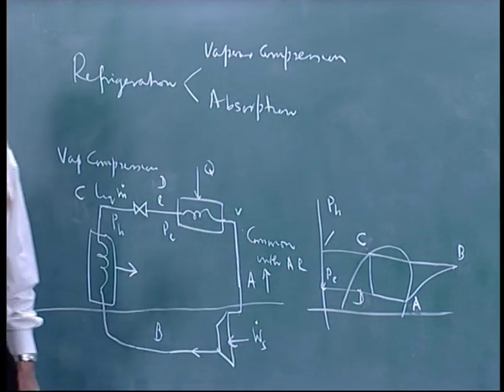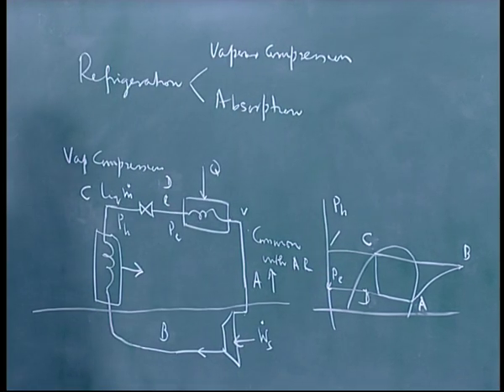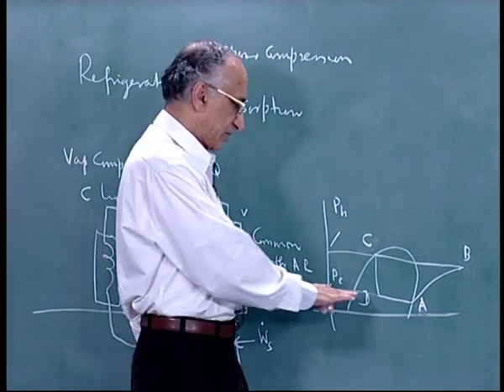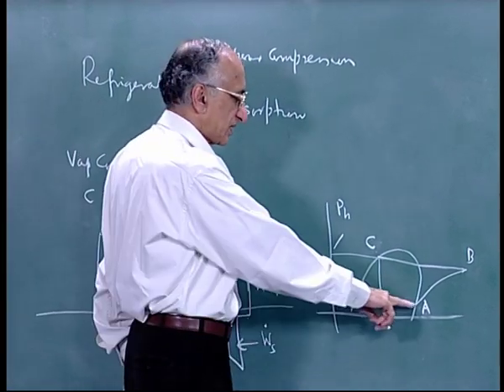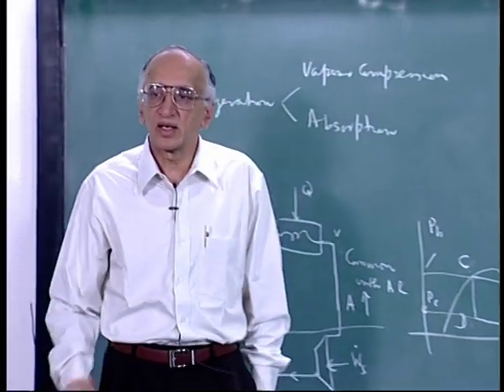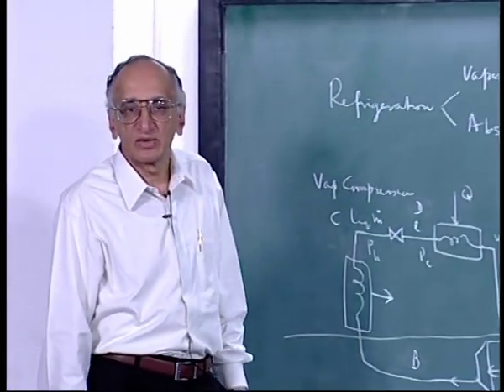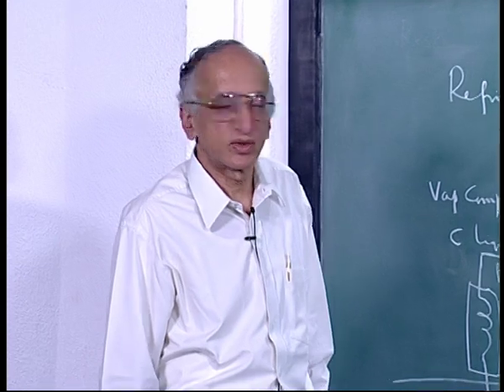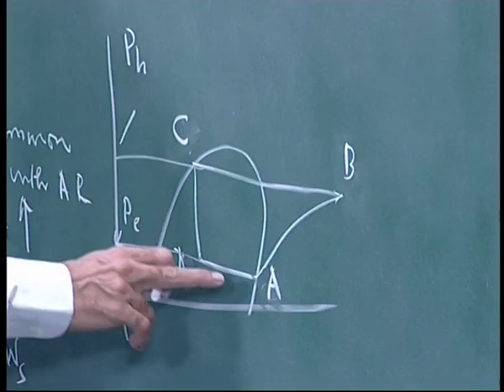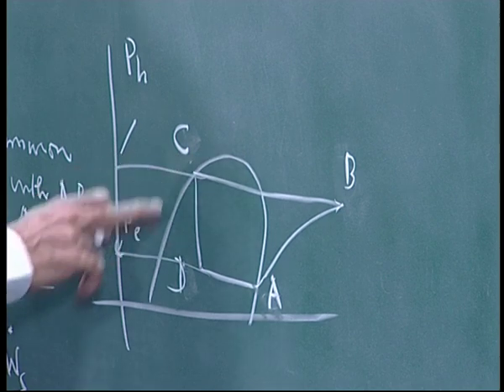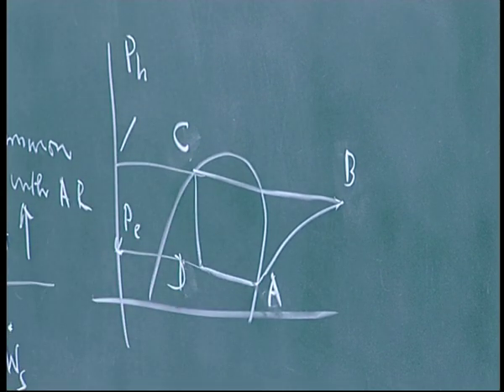The two pressures — P_high and P_low — are determined by the thermodynamic properties of ammonia and the temperature you want. In absorption refrigeration, typically used in large industrial applications, you keep the evaporator at about 10 degrees F and the condenser at roughly 80 degrees F (room temperature). The corresponding saturation pressures are the saturation pressures of ammonia at those temperatures, so both pressures are fixed. Points A, B, C, D, A — this part is the same.